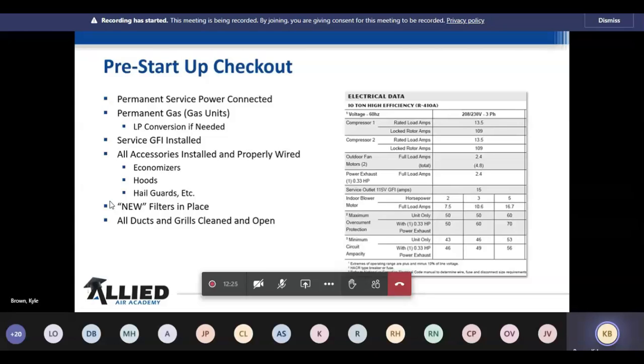But the new filters, you want to make sure they're clean, because if they crank these things up and they did a lot of work down in the given space at the bottom, no telling what it's pulled up there. So we want to make sure, especially when we start getting the static pressures, that it's good and clean. And then all your ducts are cleaned and open. That's a huge deal.